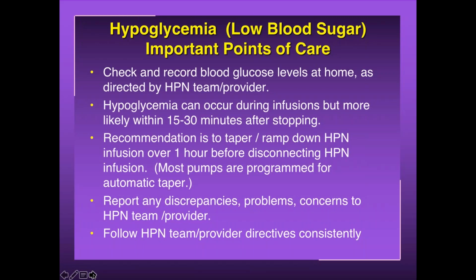Hypoglycemia can occur during infusion, like I said, with insulin, but more often it occurs if the infusion is stopped quickly, and it will happen within 15 to 30 minutes. So what we always order for our patients is that we taper, ramping down the HPN infusion over about an hour before we disconnect. And the pumps are programmed to do that, to automatically taper, which is why it's so important that your pump knows the correct volume to infuse, because it's programmed to taper it.